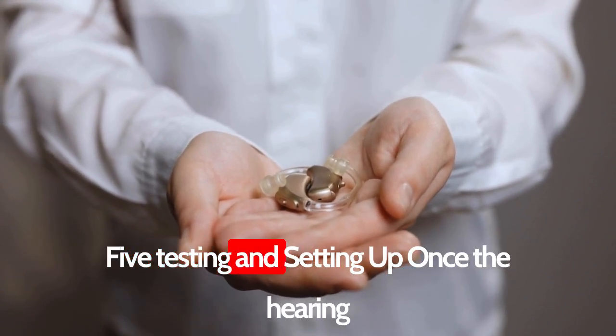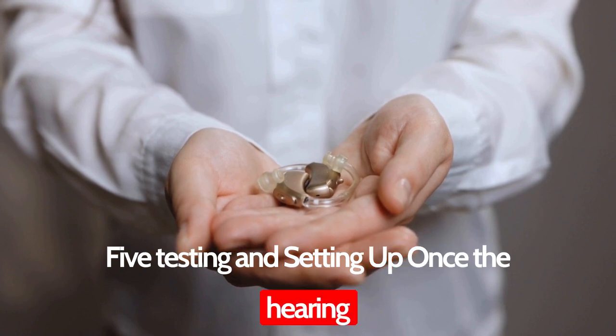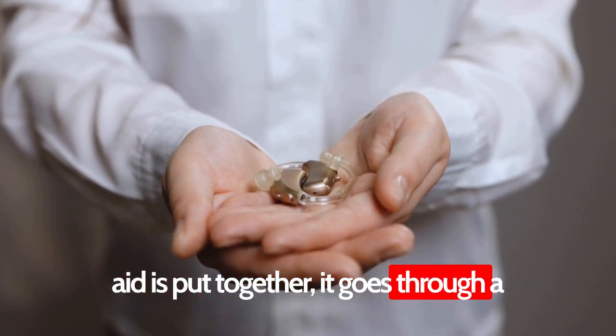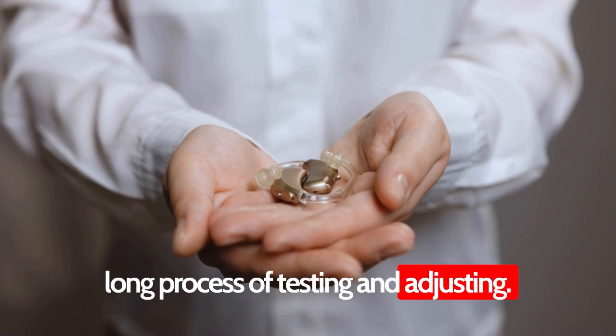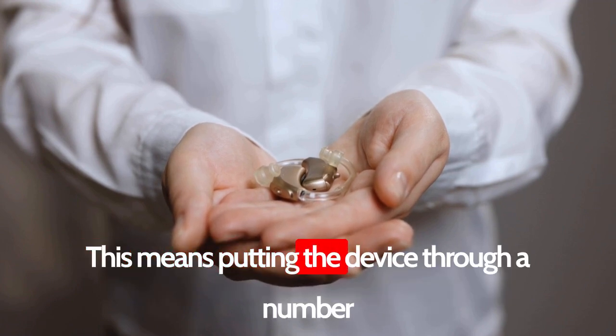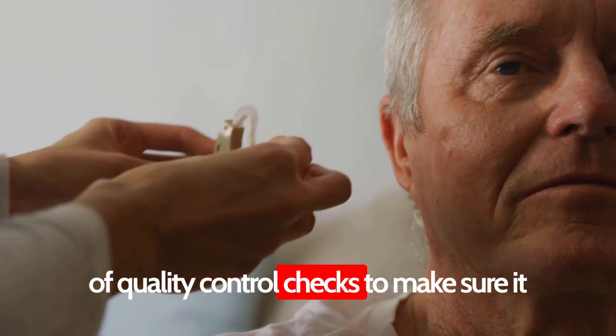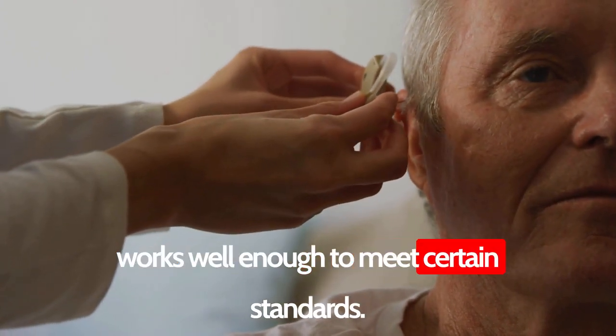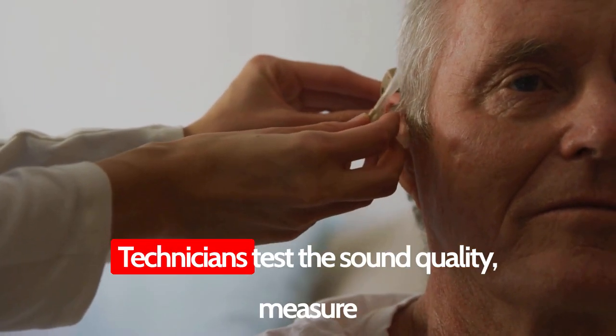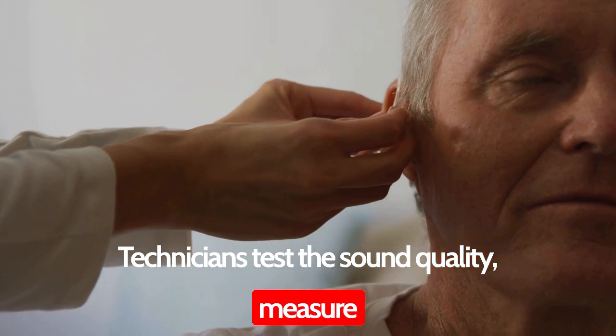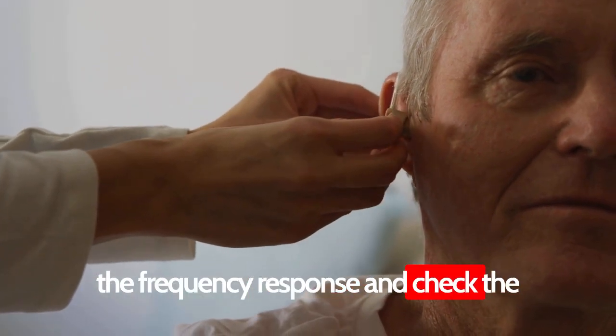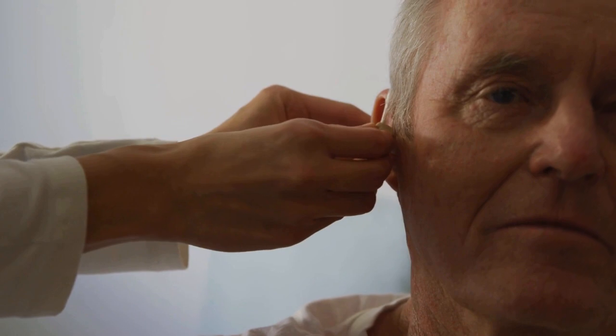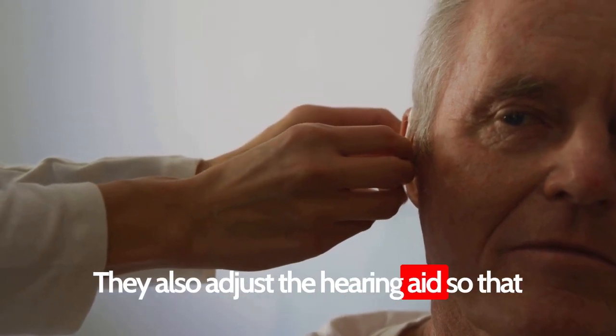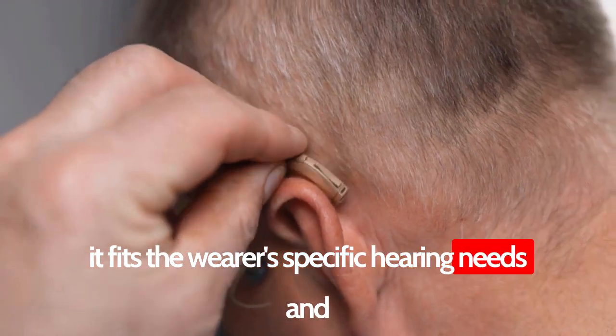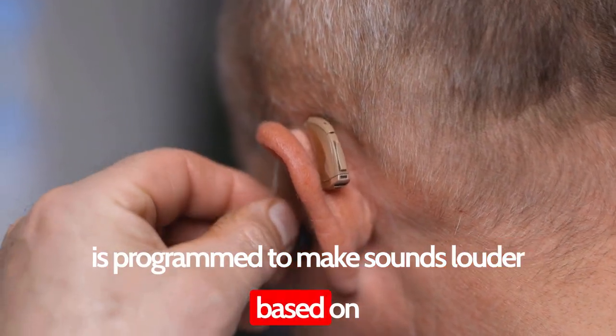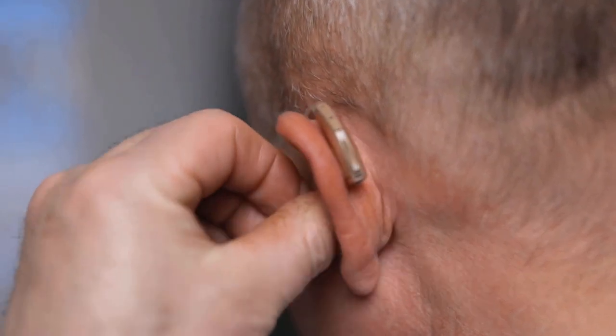5. Testing and setting up. Once the hearing aid is put together, it goes through a long process of testing and adjusting. This means putting the device through a number of quality control checks to make sure it works well enough to meet certain standards. Technicians test the sound quality, measure the frequency response, and check the correctness of the amplification. They also adjust the hearing aid so that it fits the wearer's specific hearing needs and is programmed to make sounds louder based on the person's hearing loss profile.